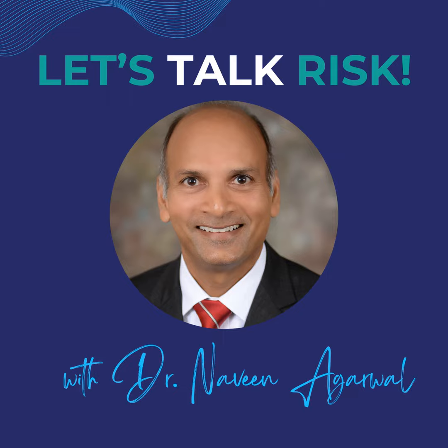But anyway, one of the things I can think of, and you're right, starting in feasibility, and especially it's required if you're going to do any clinical trials, is to have a risk analysis done before the device is exposed to customers. But where you can start is thinking about and going back to the Annex A 24971 questions about the characteristics related to safety, and then what standards apply.